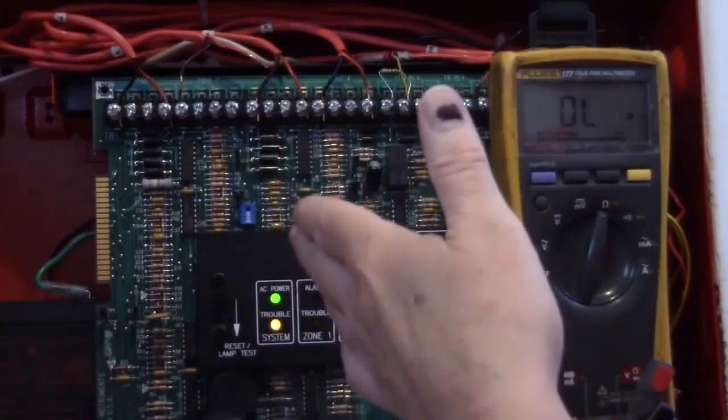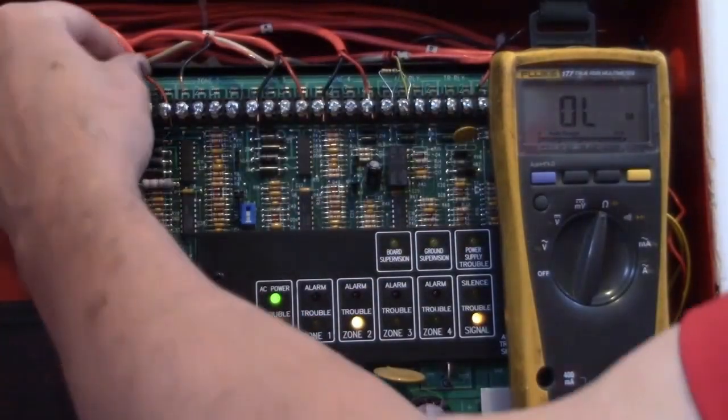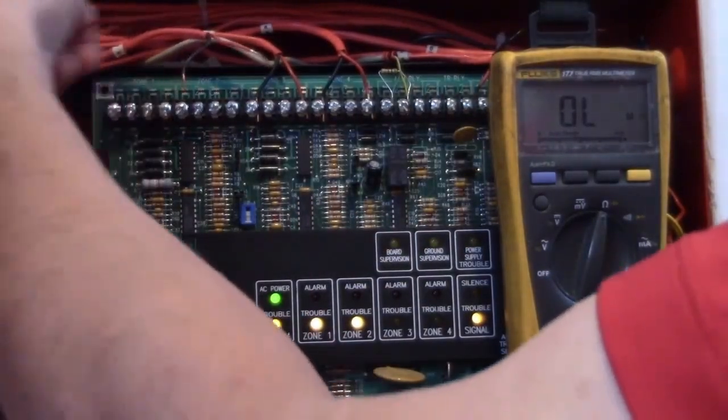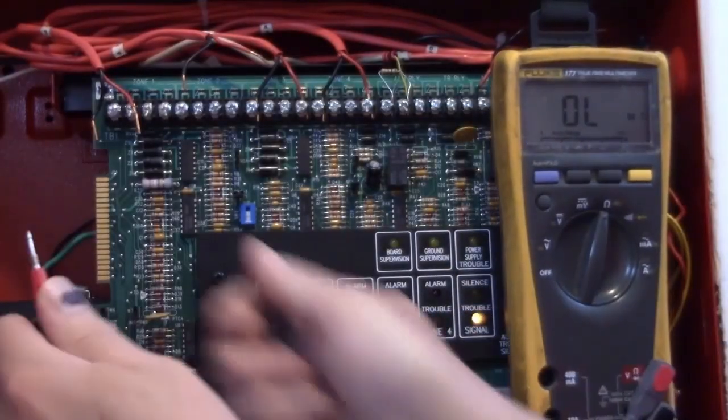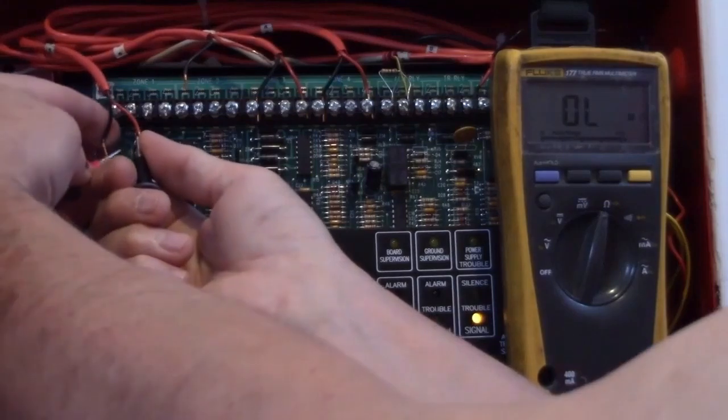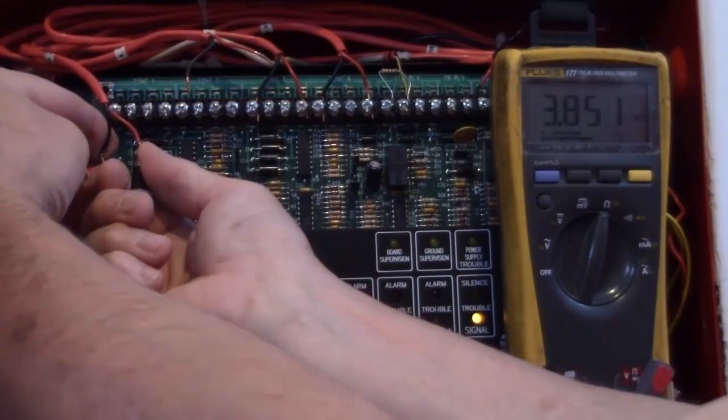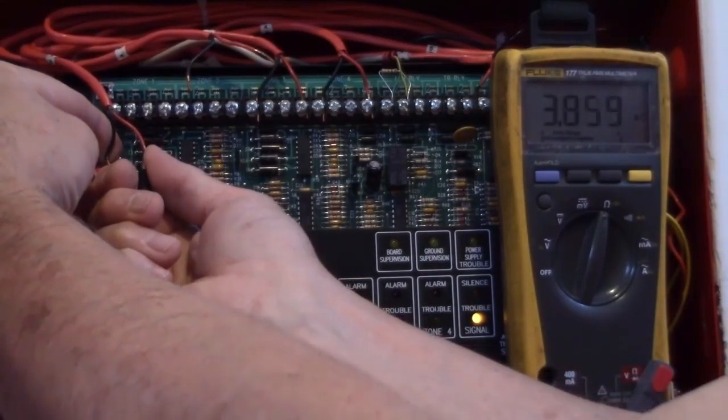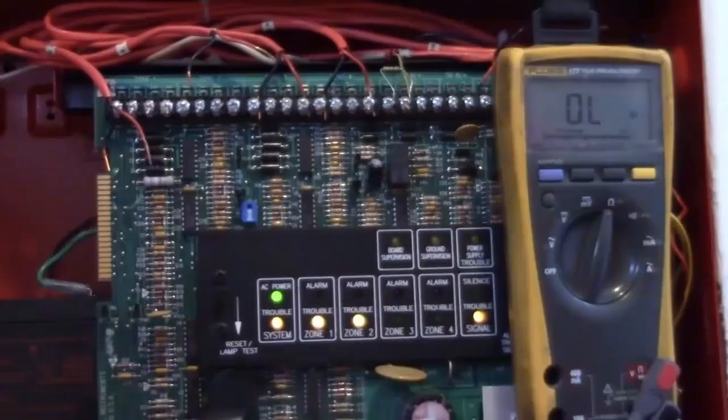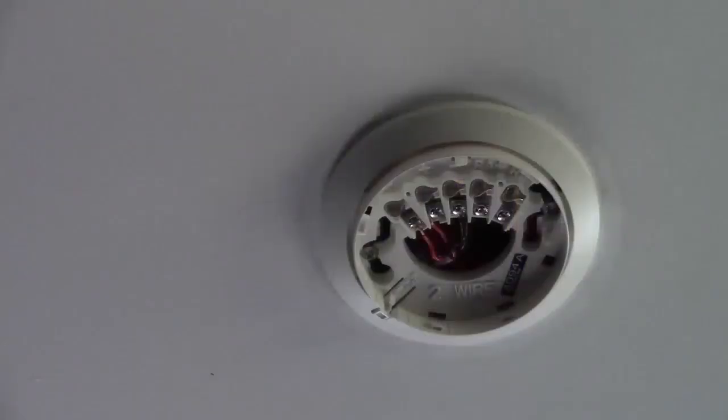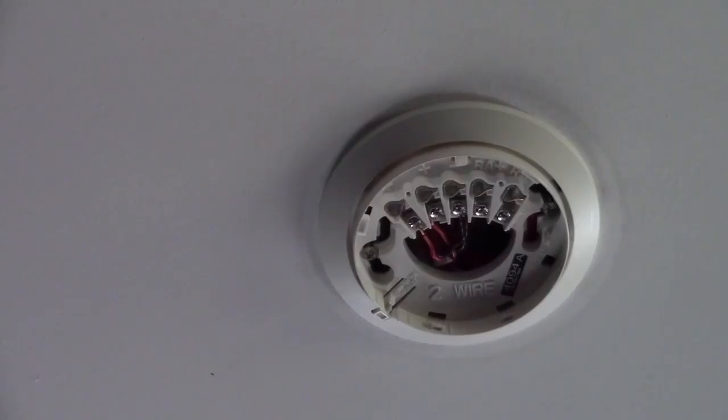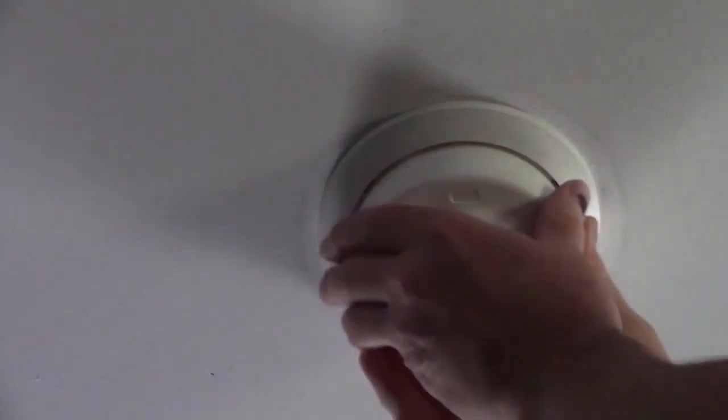If you're unsure what the resistance should be, what you can do is remove a zone that's not in trouble, measure the resistance of that circuit and you'll have that as a comparison. When we measure a zone that was in normal condition, we see that it was about 3.9 kiloohms. Make sure you record what the normal zone voltage should have been and what the end of line resistor value should be. While troubleshooting, you discovered a smoke detector had been removed. Reinstalling that device should restore the system to normal.